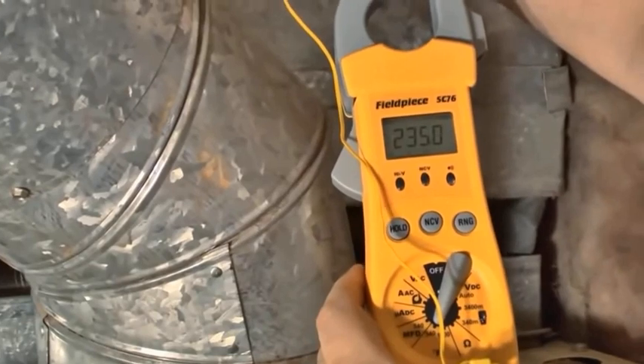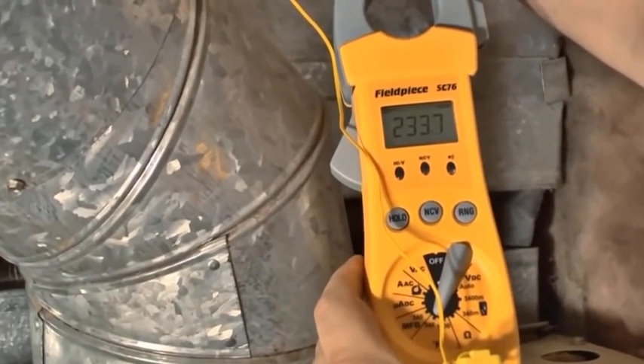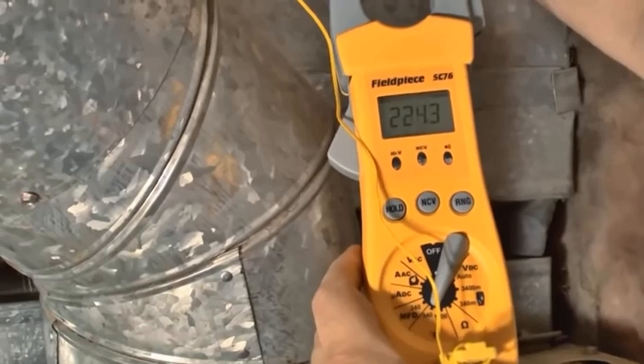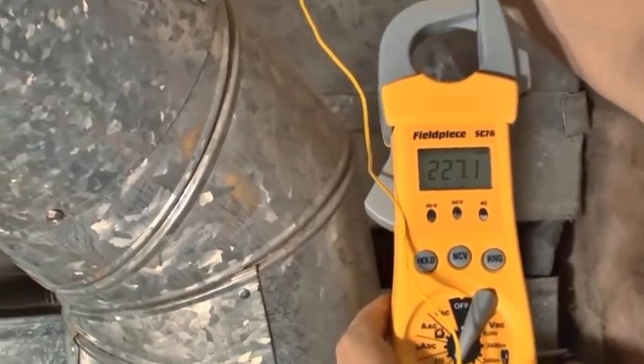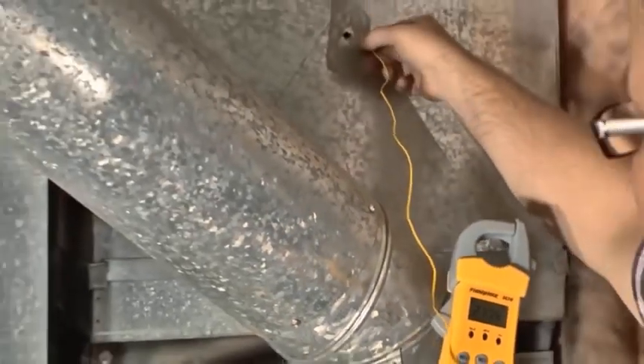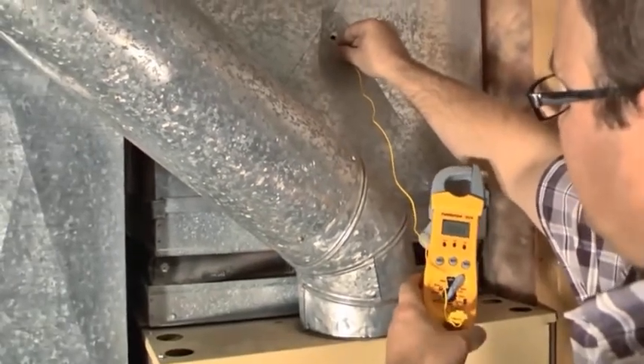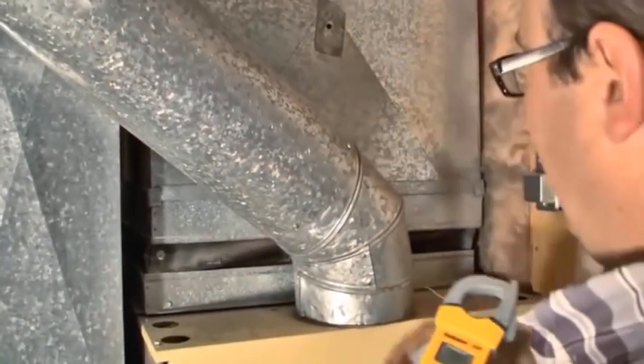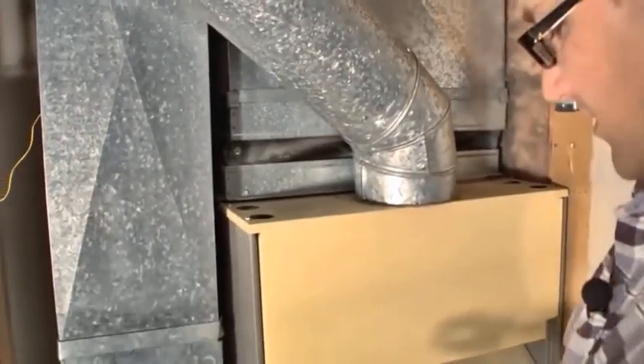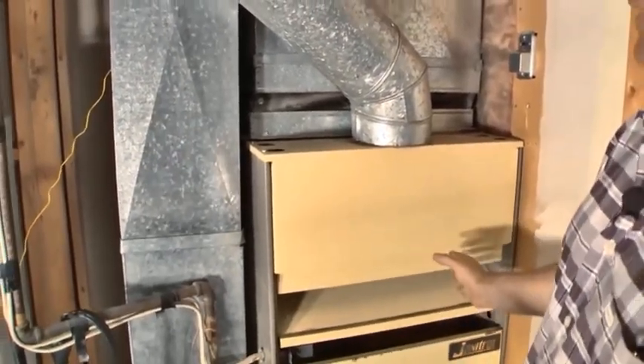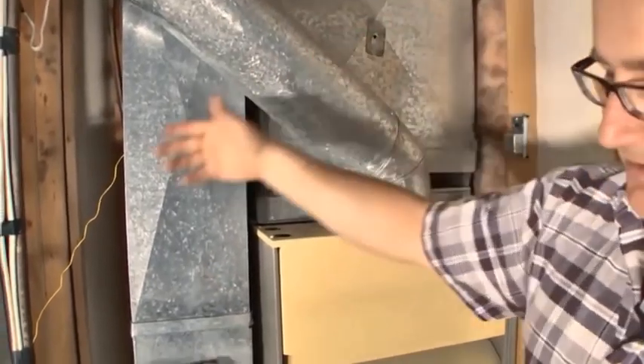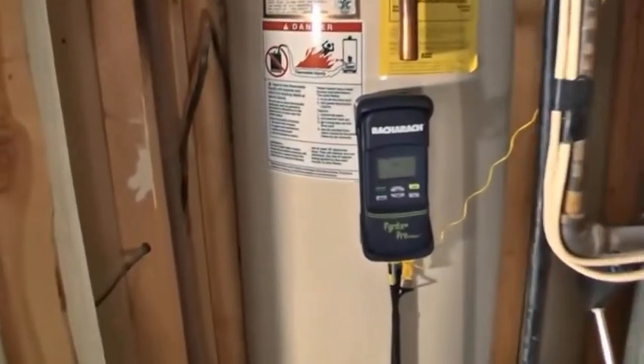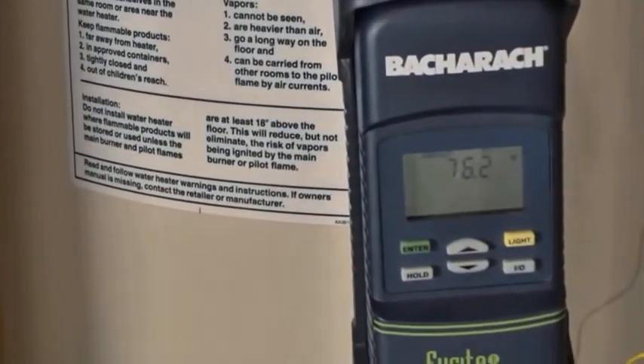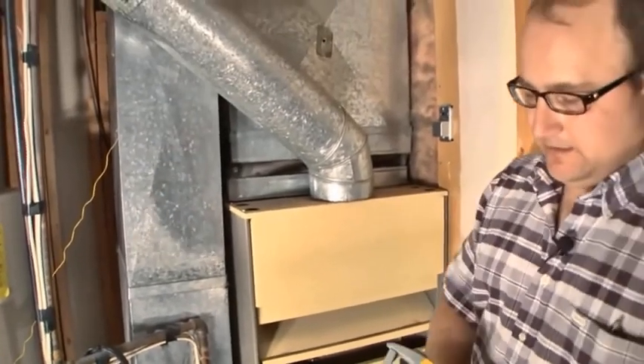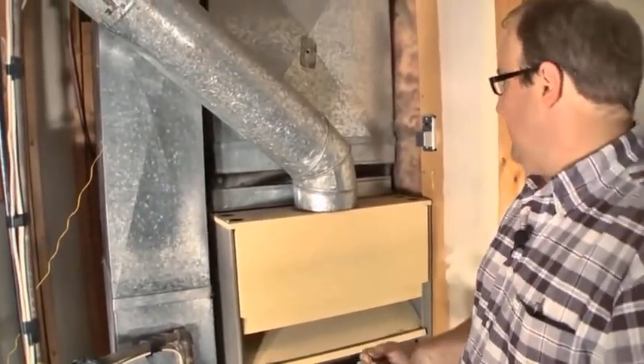Looks like we have about 235 degrees, 230 degrees is our air temperature. We'll call it 230. That's a really high heat rise, and it's more than likely caused by the plugged filter causing that high heat rise. So 230 there, 75 here. That gives us a 155 degree heat rise. We like to see a 30 to 50 degree heat rise, no more than 80.